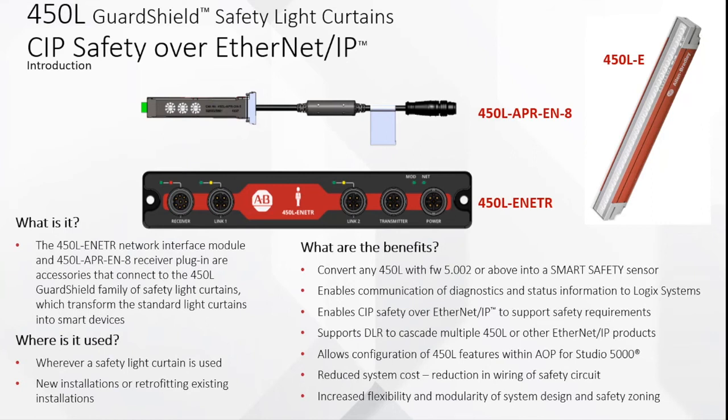It can be used for new installations or retrofitting existing installations. You need to use the 450L with firmware 5.002 or above. It converts any 450L into a SMART SAFETY sensor and enables communication of diagnostic status information to Logix systems, enabling Safety over Ethernet. It supports DLR to cascade multiple 450L and other EtherNet/IP products. It allows configuration of the 450L with Studio 5000 — which is a big plus — using the AOP, which makes it very easy. It also reduces system cost through reduction in wiring of the safety circuit.